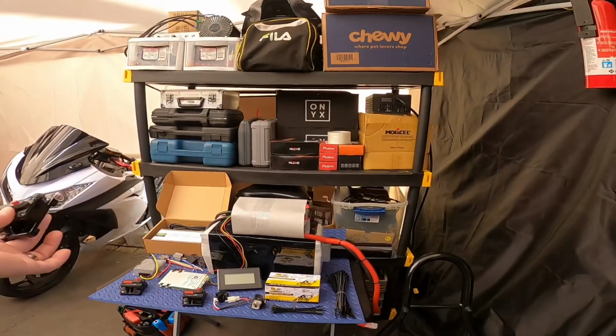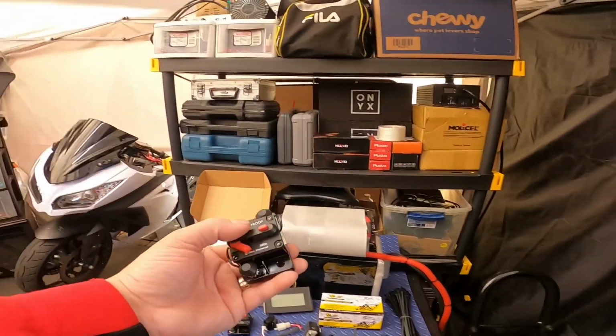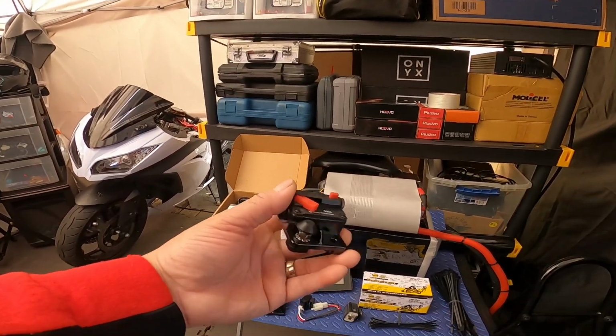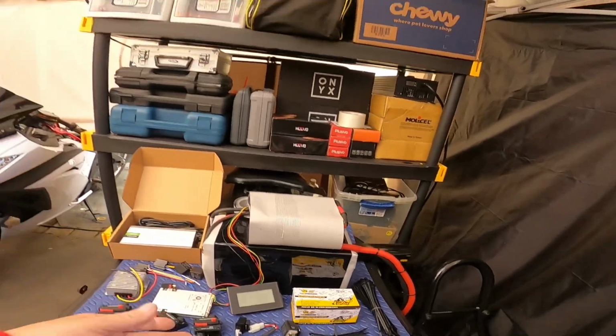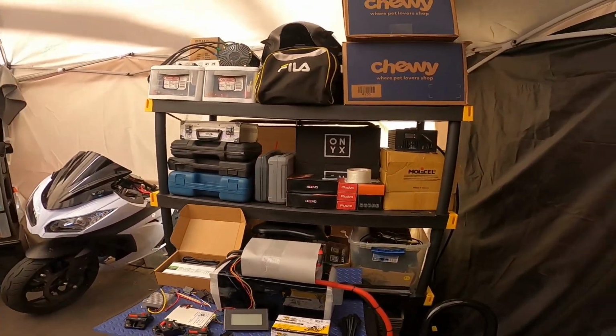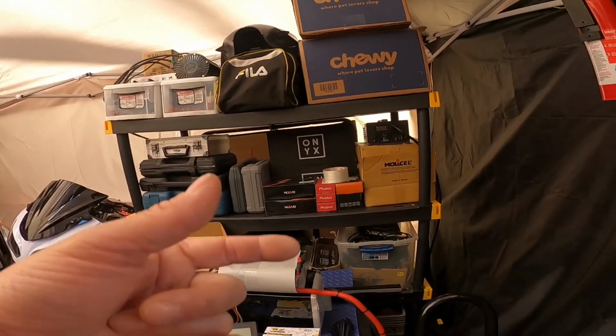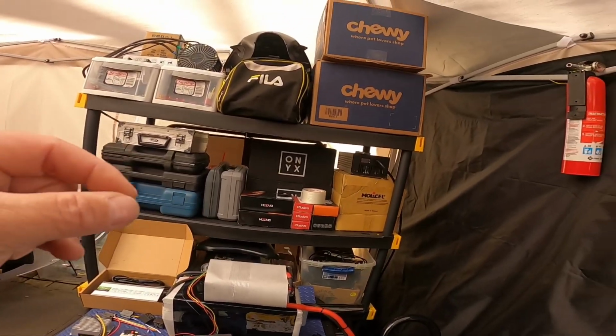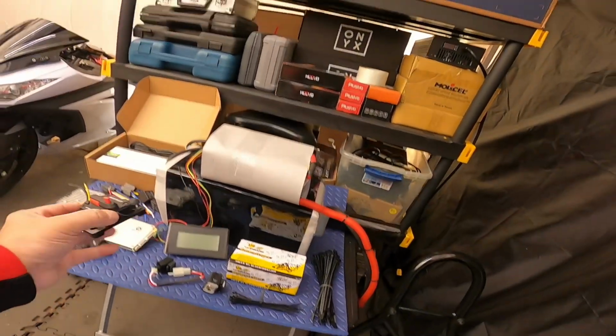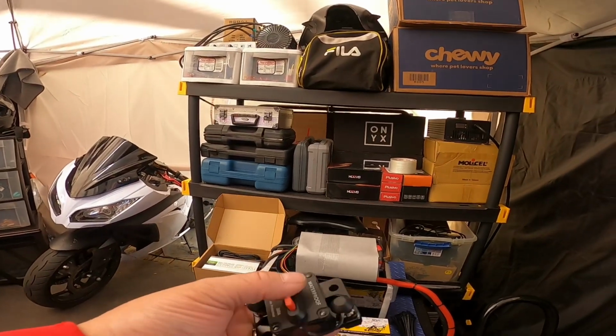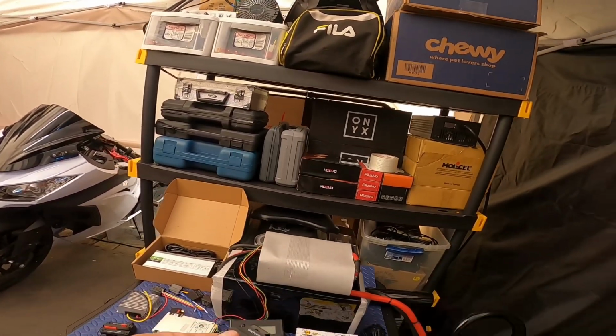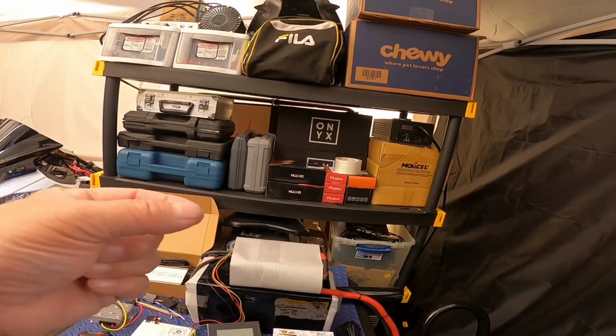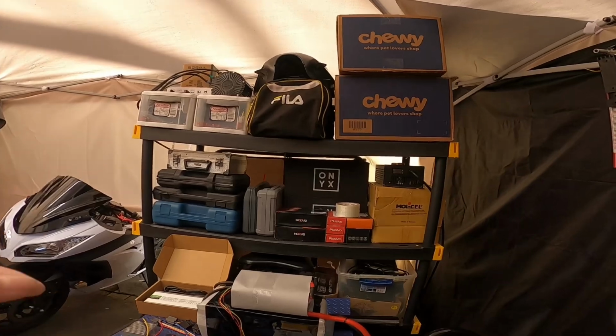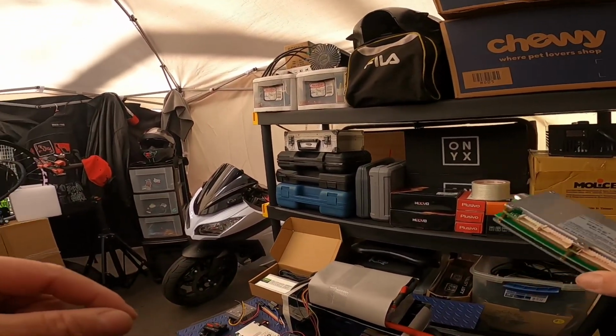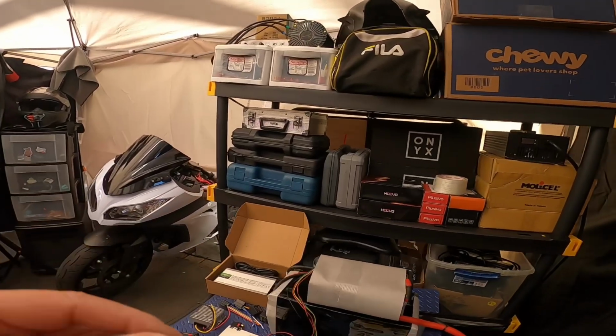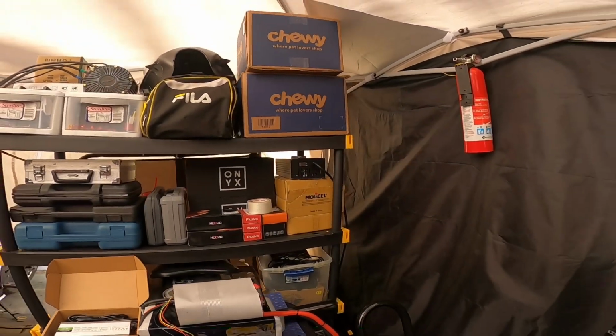Okay, why would you attempt to pull 300 or 400 amps through a supposedly 150 amp circuit breaker? Now, although some of those circuit breakers don't trip and allow current to flow through there, that current is only squeezing through those breakers at a very high resistance, because whatever the metal connections they're using in there, sometimes it's coiled wire, sometimes it's little blades. I mean, it cannot handle the same amount of current flow as those power wires at the same resistance. So that's going to be a bottleneck.